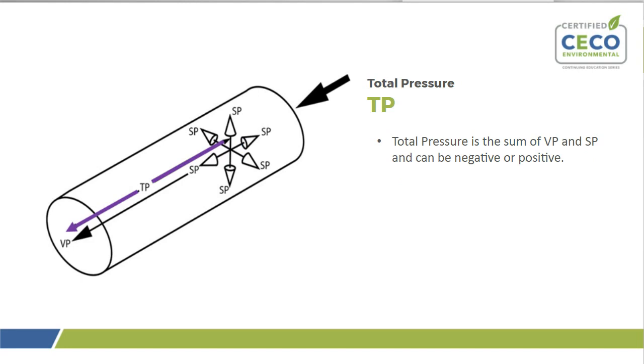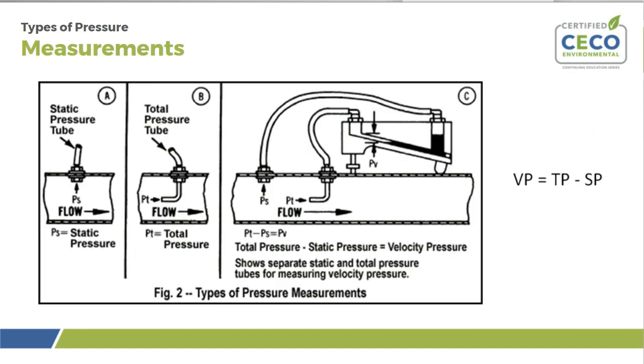Finally, total pressure is the sum of our velocity pressure and static pressure and can be negative or positive. Figure A is illustrating the pressure contained within a duct, the static pressure. Note the pressure tube does not extend into the duct. This pressure represents the pressure difference within the duct from atmospheric pressure. Figure A is static pressure.